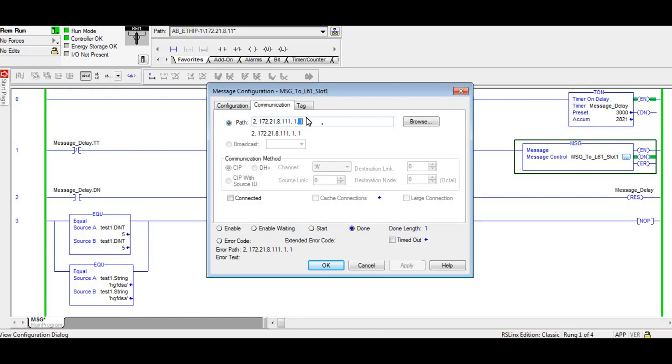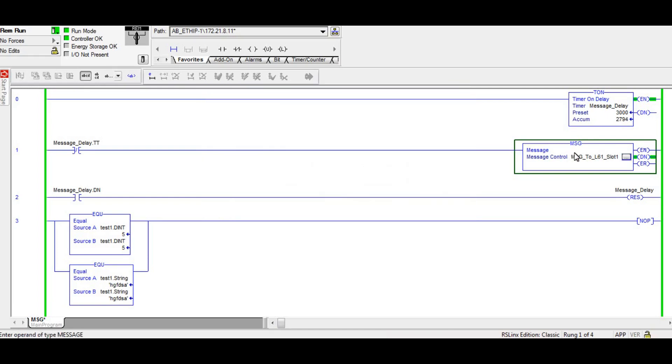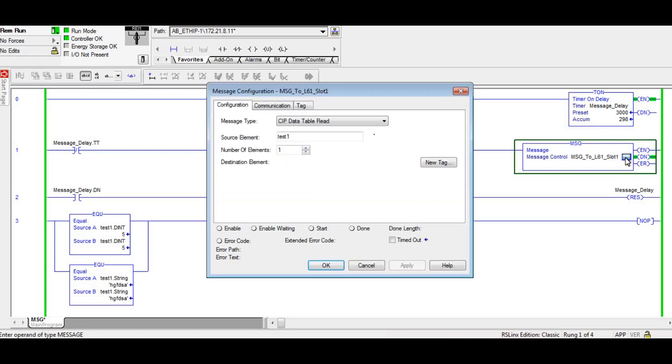And that's because this is slot one, not slot zero, which is where most people put their PLCs. I just happen to have two PLCs in this rack and I want to talk to the second one which is in slot one. All right, so you can see this message is completing, you're getting the done bit.